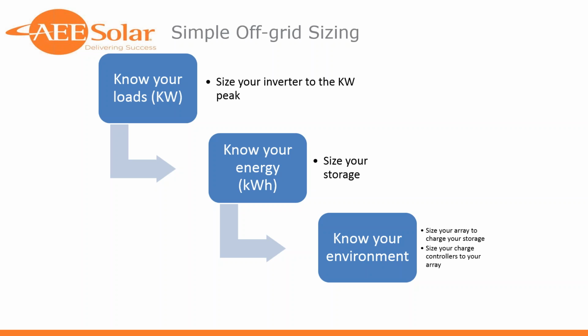That's going to size your inverters, to know how much power I need to support in the worst case scenario at any given time. What's the continuous current going to be, and what's the peak or surge current going to be? From there, we know our peak number. We know, by doing this load study, what our energy number is going to look like in a given day.